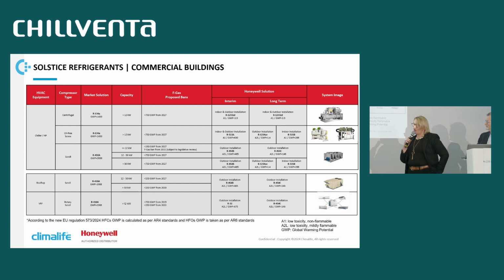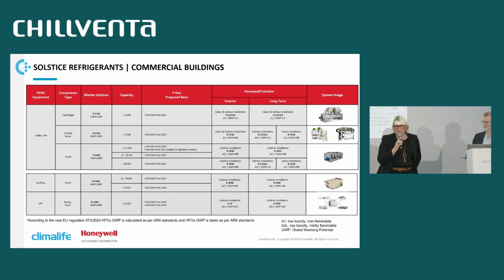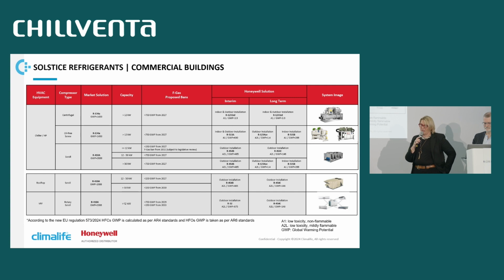For VRF, there are also two bans with F-gas regulation. The first will be in 2029, requiring a GWP less than 750. And in 2033, we need to go to very low GWP, less than 150. But the solutions exist. All of them are available today, so we can switch now if we want to decarbonize this industry.